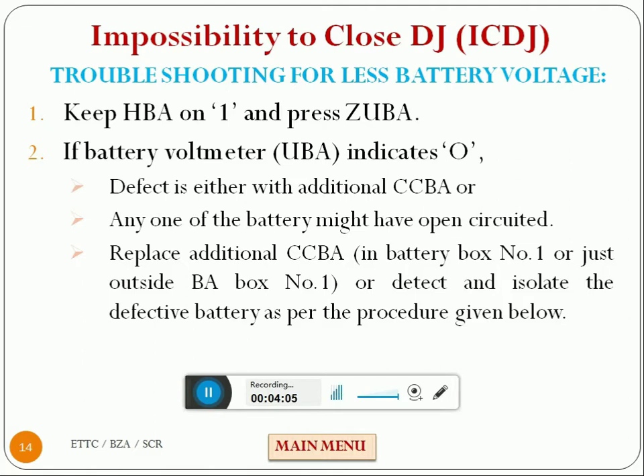So we have to check the signal lamps. If signal lamps are also not working, the trouble is in battery, HBA, additional CCBA. So additional CCBA we have to replace, HBA 2 or 3 times. We have to operate it and keep it in one position. If not successful, check battery one by one.